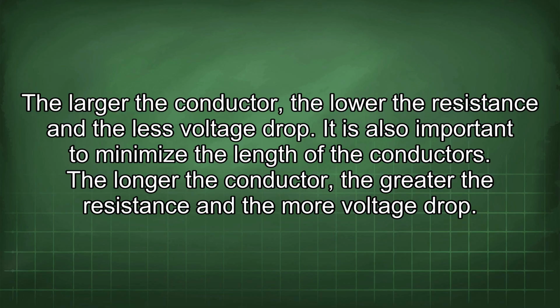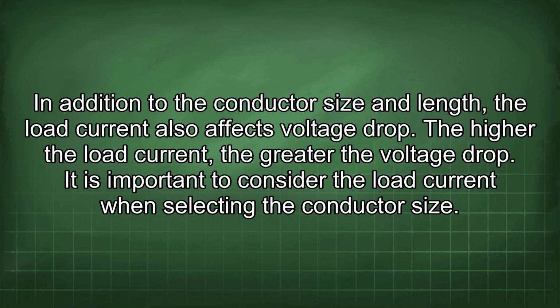It is also important to minimize the length of the conductors. The longer the conductor, the greater the resistance and the more voltage drop. In addition to the conductor size and length, the load current also affects voltage drop. The higher the load current, the greater the voltage drop. It is important to consider the load current when selecting the conductor size.